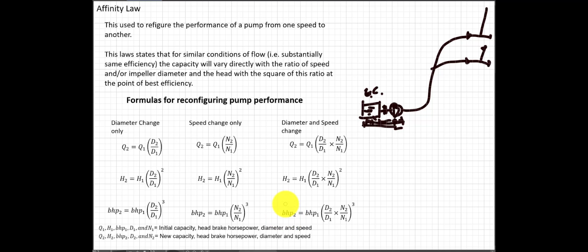So we have here a sample problem. We have a pump operating at N1, I'm going to write it here, with the value of 3,550 RPM, and has a performance as shown in the solid line. So we have here percent efficiency, your y-axis which is head in feet, and your capacity. This one is your TDH, or total dynamic head, at this side, and here your capacity, which is the volume flow rate. Now, calculate the performance of the pump if the operating speed N2 is increased to 4,000 RPM. Okay?